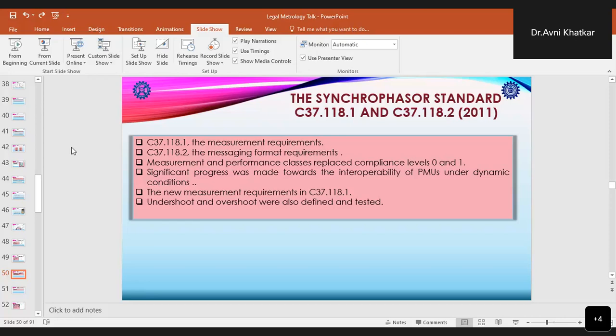Also, the synchrophasor definitions and formulas were upgraded for phasors, frequency, and rate of change of frequency. It added specifications for the dynamic performance also, and testing over a temperature range, that was also incorporated in order to refine the requirements of the steady state performances. And the new measurement standard, that is C37.118.1 standard, included some other requirements like frequency ramp test, along with it the assessment of response time, which was related to the window length, was also included.